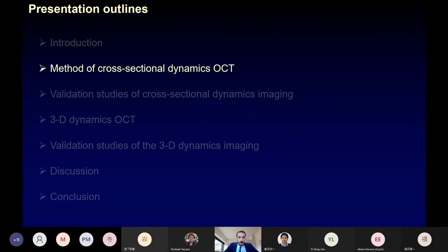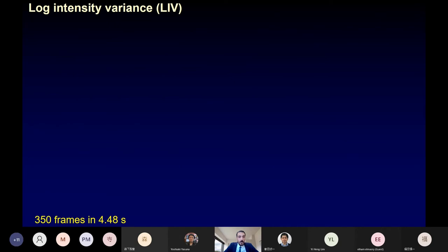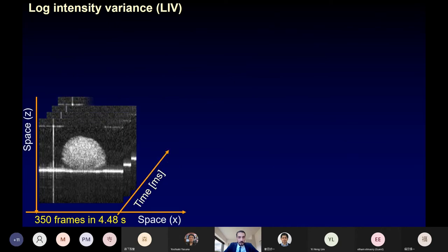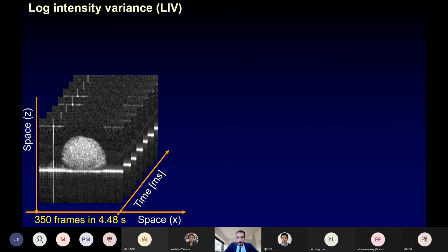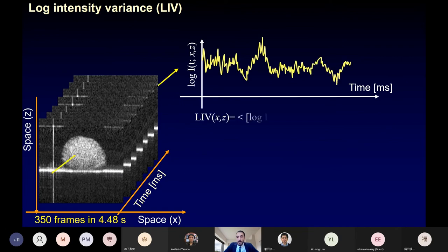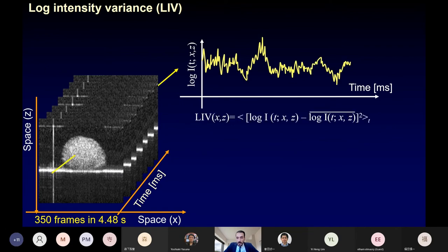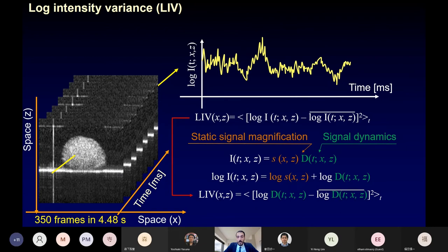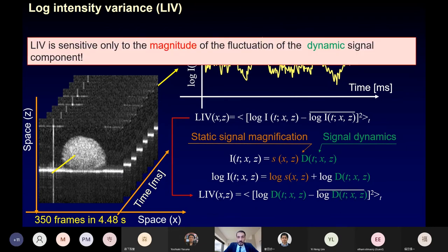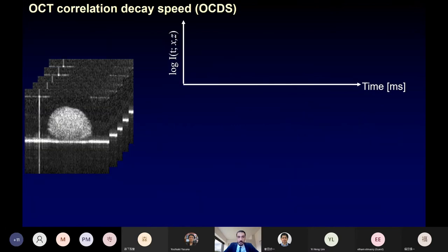Our method for cross-sectional dynamics OCT is based on rapid acquisition of an OCT time sequence at the same location in the tissue, with signal analysis performed by two algorithms. The first is logarithmic intensity variance (LIV), which is the time variance of the log-scale intensity. Modeling intensity as i equals s times d, where s is a static signal magnification and d is the signal dynamics, taking the log and computing the variance gives LIV, which is sensitive to the magnitude of the fluctuation of the dynamic signal component.